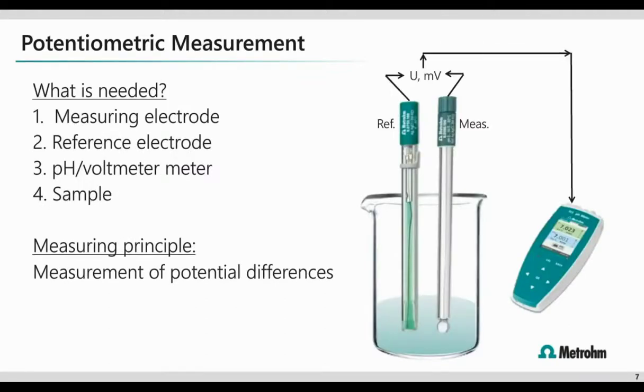If we look at what is needed to make the measurement, the same 4 components are needed to complete the circuit for every example. So we need 2 measuring sensors. We need an indicator or measuring electrode that gives the potential dependent on the composition of the sample solution, okay? The other is a reference electrode. So this will supply a constant potential, which is as independent as possible from the sample solution, okay? Next, we'll need a meter or other device to collect that signal and convert it into something that makes sense to us. And then lastly, we've got to have a sample to complete that full circuit.